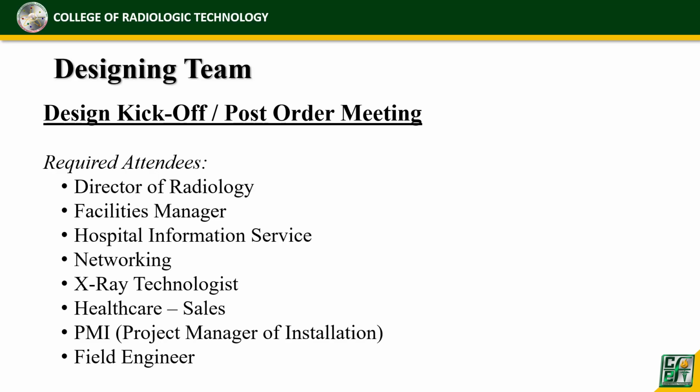Okay. So designing team. These are the members of the designing team. Okay, the director of the radiology department, which is the radiologist. Okay, facilities manager of the hospital, hospital information service, networking, representative of the IT, yung networking. Okay, then of course the rad tech. In this case, usually chief tech ang kasama. Okay, then healthcare sales nung machine. Then the project manager of installation. So this manager is in charge of installing the machine and other parts of the X-ray system, and of course the field engineer.